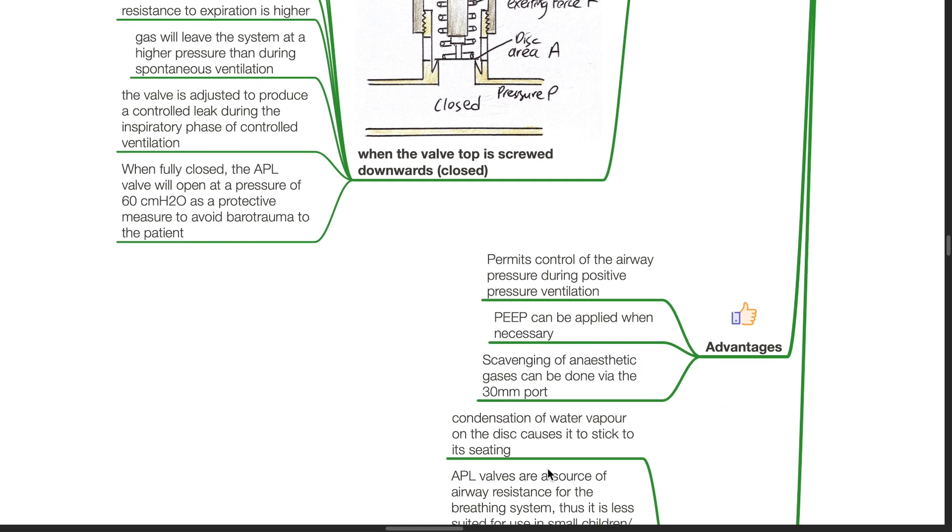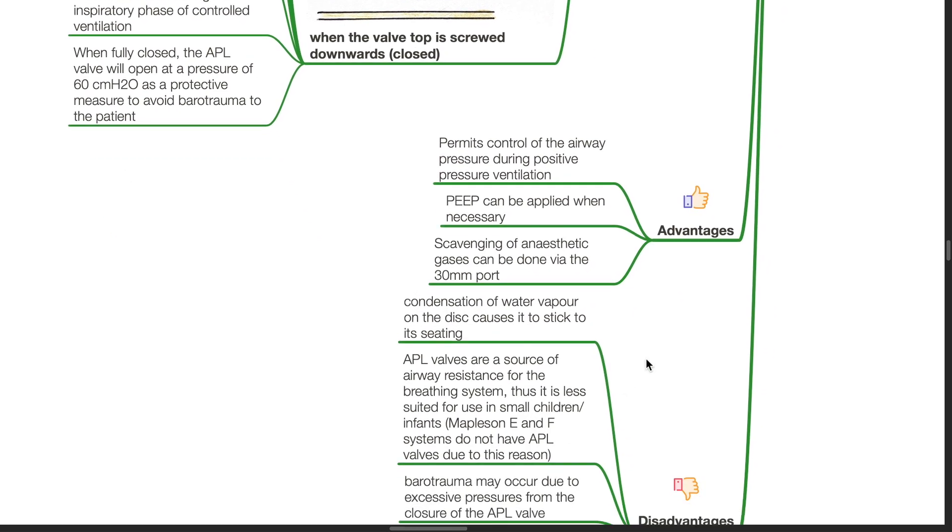Advantages of the APL valve. It permits control of the airway pressure during positive pressure ventilation. PEEP can be applied when necessary. Scavenging of anesthetic gases can be done via a 30mm port.